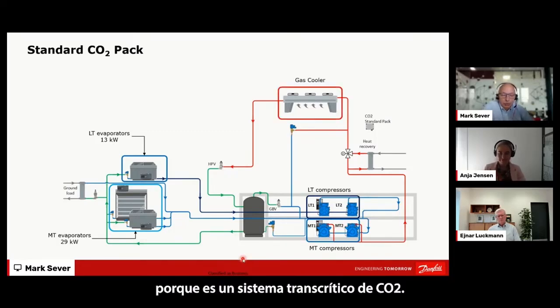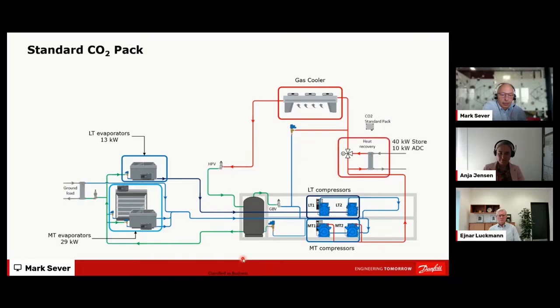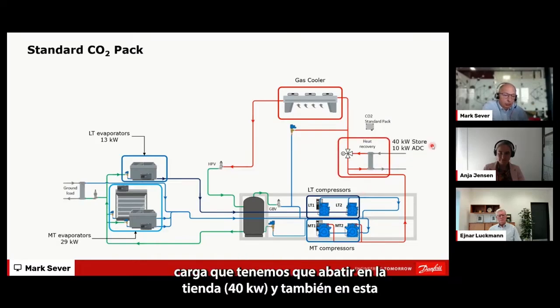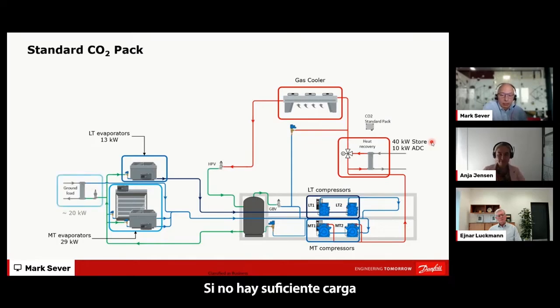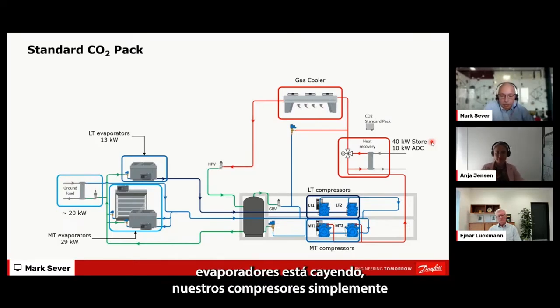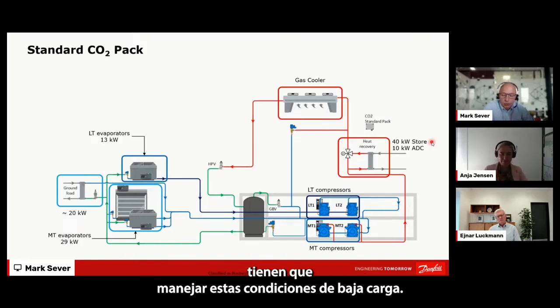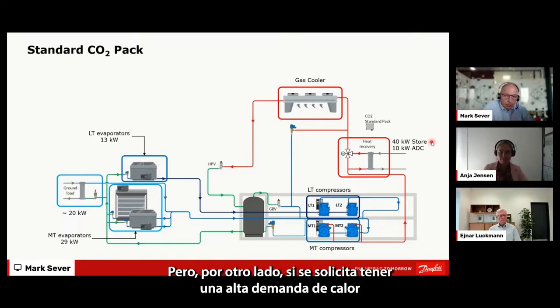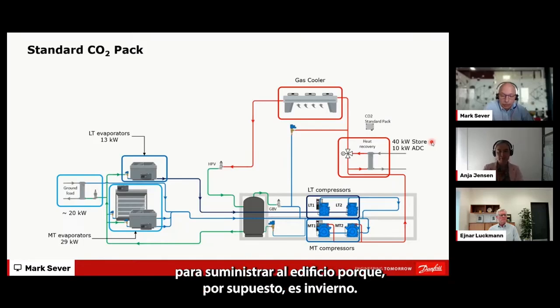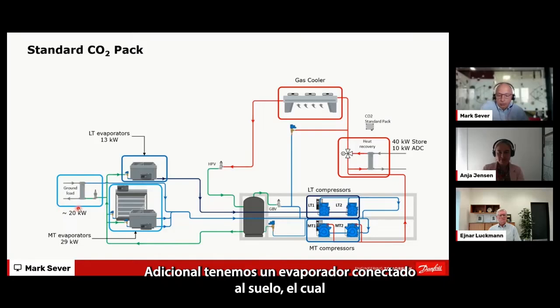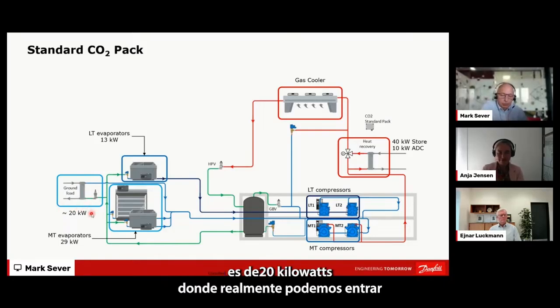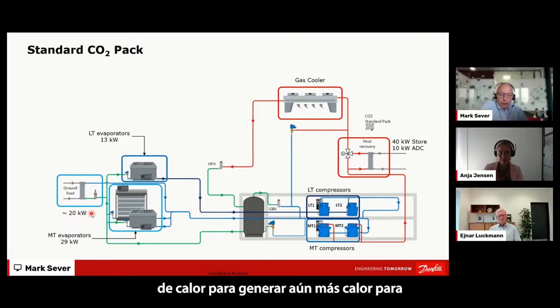Then we have a gas cooler, because with a CO2 transcritical system we no longer call this a condenser but a gas cooler, because we are going above the transcritical point. Then what we applied here is heat recovery. This is the load we have to manage in the store and also in this application, part of the building. If there is not enough load in the system, especially during winter time, when the load on the evaporators is dropping, our compressors have to manage these low load conditions. But on the other hand, we are requested to supply a high heat demand to the building, because it's of course winter. Then we have an additional evaporator connected to the ground. It's at a level of 20 kilowatts, where we can get into a kind of heat pump mode to create even more heat for the system and deliver it to the building.